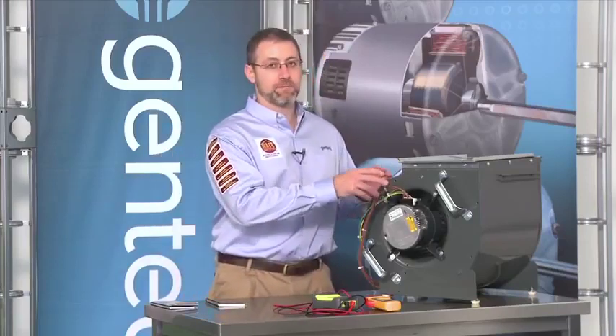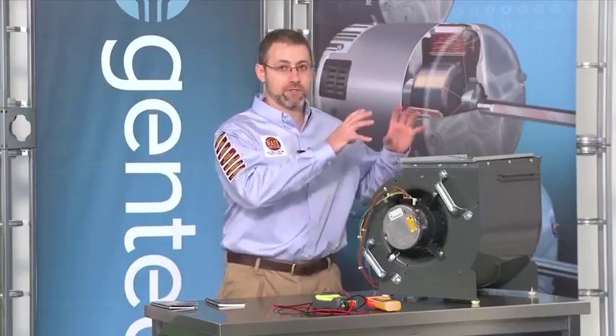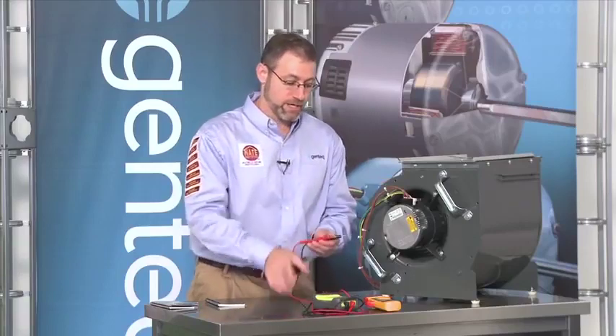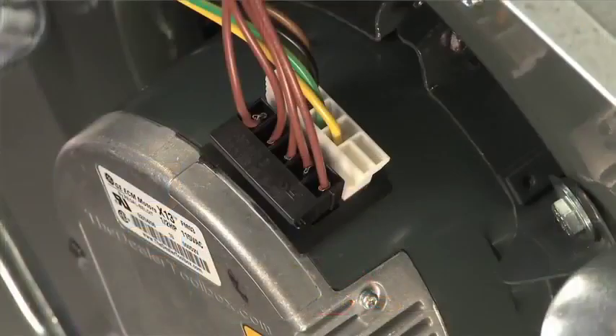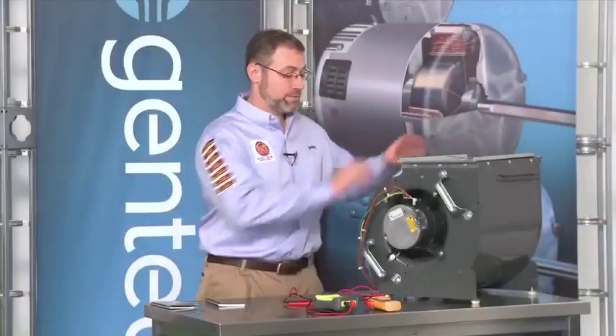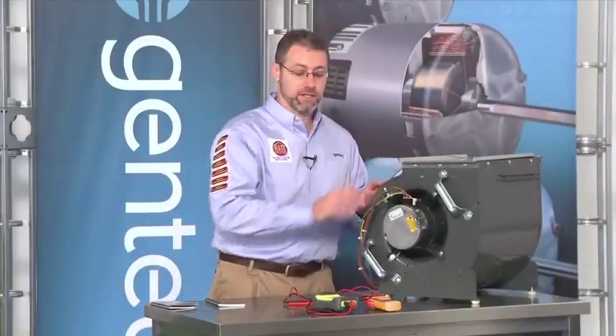Before we can troubleshoot the power going into the motor, we would have to turn the power off to the HVAC system. We don't want to simply take our meter leads and try and push them in through the back of these connectors, because that could damage the connectors and or damage the wires. So we'd want to turn the power off, disconnect our connectors, and check the power that actually meets the motor on the other side.